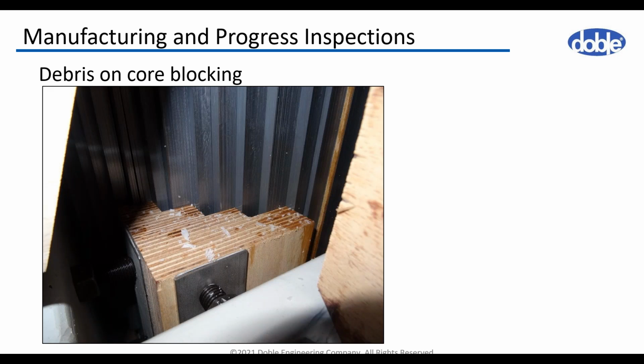Debris on the core blocking. Yeah, this is another issue. They could easily be spread all around the active part with the oil flow when this unit is filled with oil. So we would like to have the unit perfectly clean before tanking.